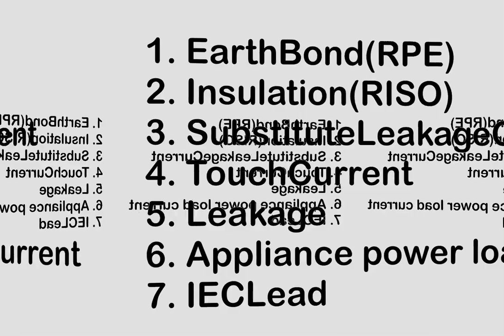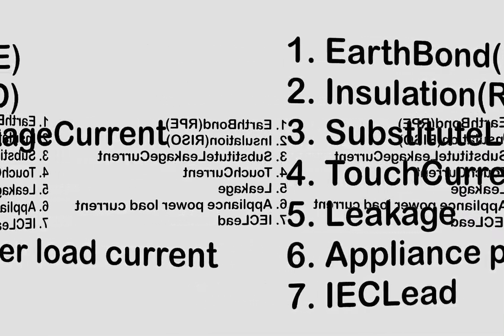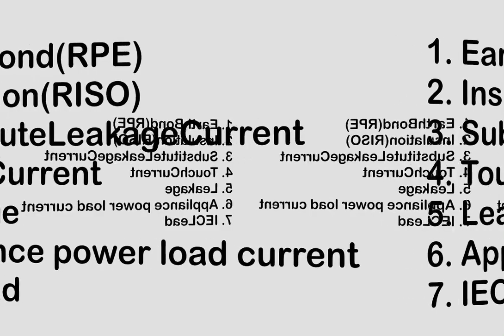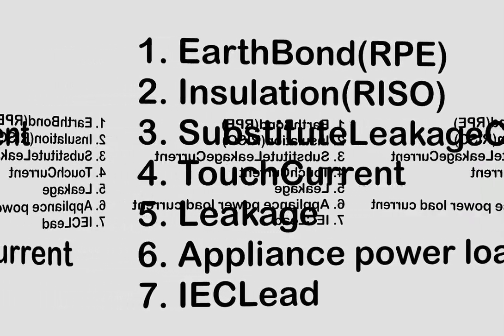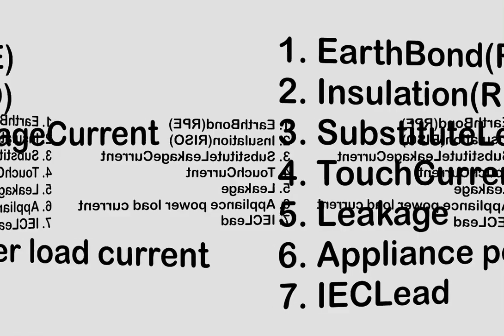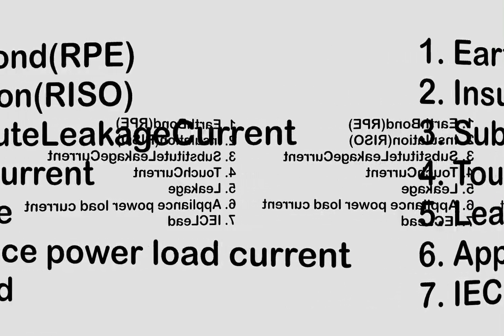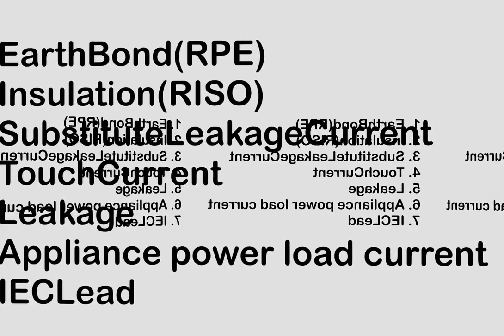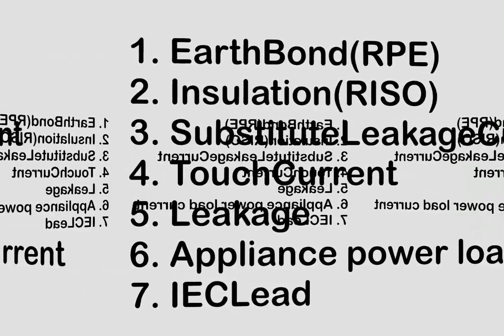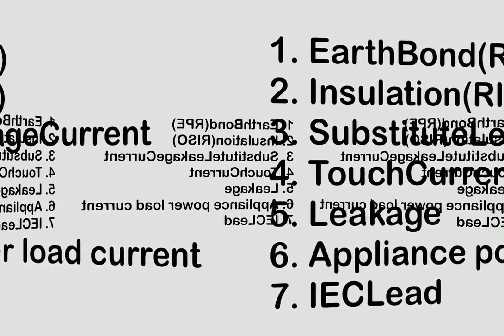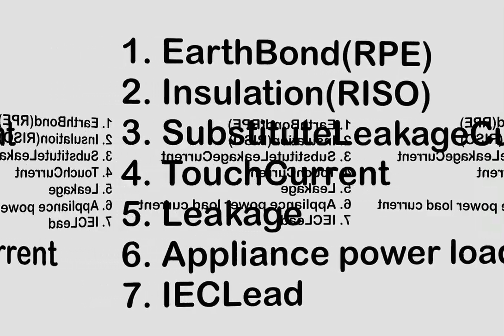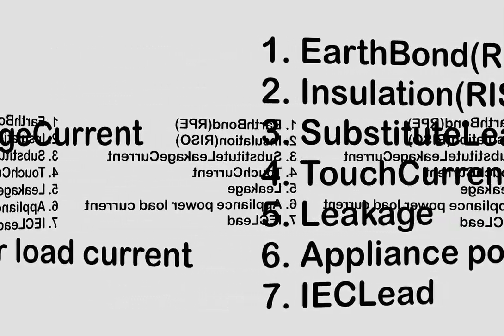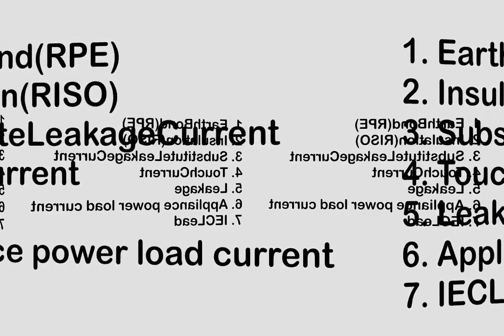Now we are going to discuss what we need to do during the PAT test. There are seven things to carry out. First is the earth bond test, also called the RPE test. The earth bond test measures the resistance of the earth from the pin of the main supply plug to the earth body of the appliance, and indicates how good the connection is. Second is the insulation test, with the shortcut name RISO. This test measures the total resistance between any two points separated by electrical insulation.